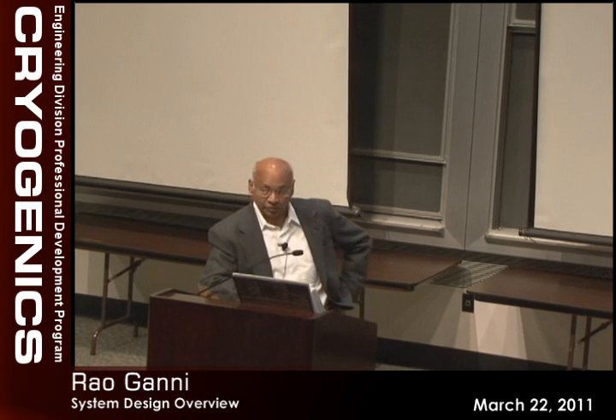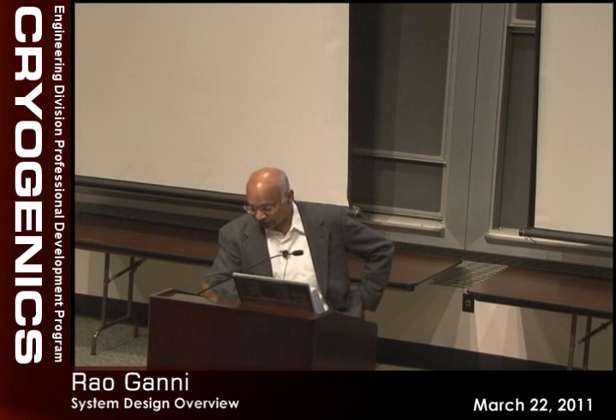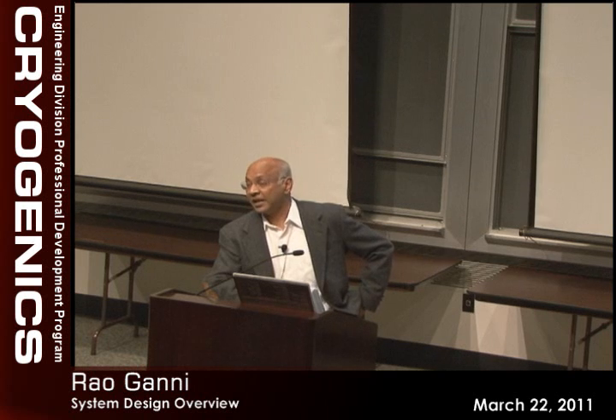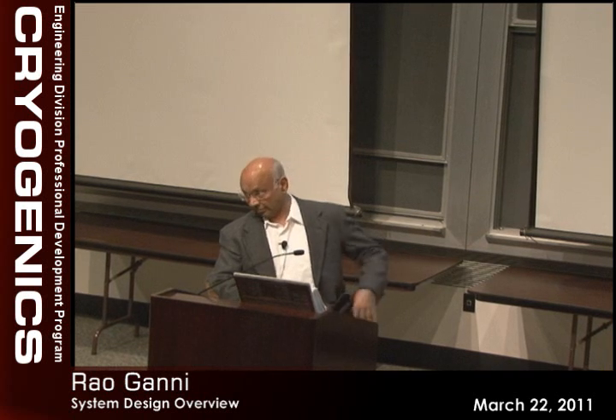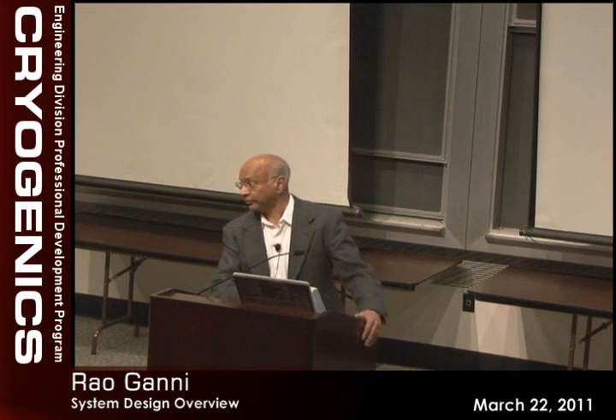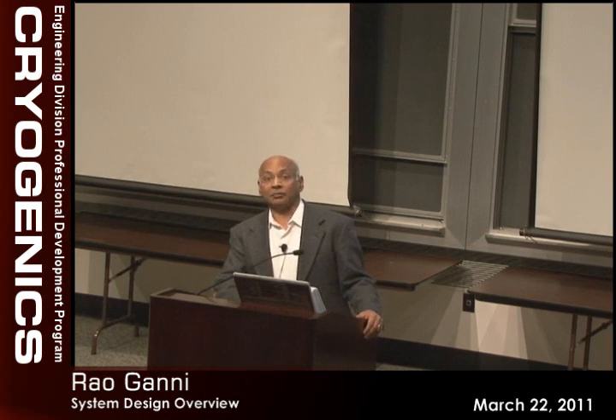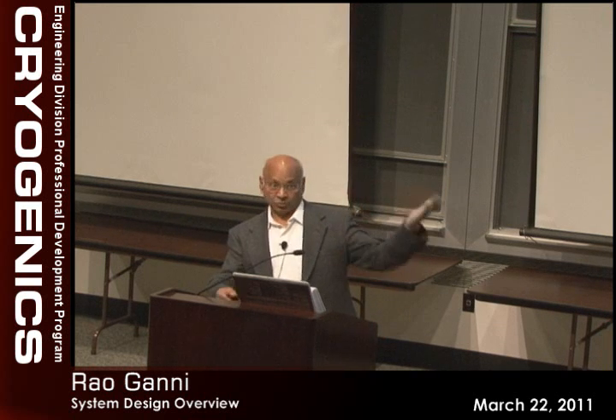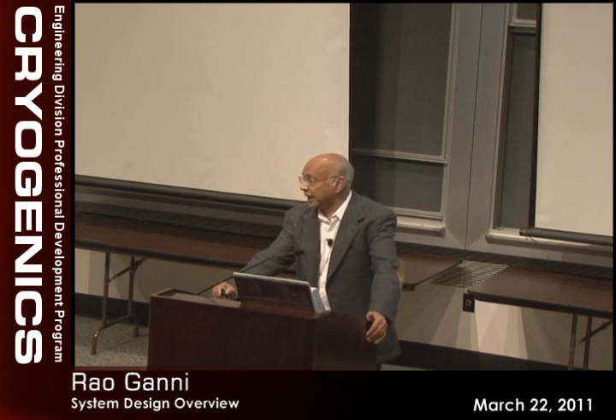The other thing we do not pay attention to is the pressure rating. It comes in a few different ways. One is that there are places where we need a very high pressure rating, like the Bureau of Mines liquefier, which we stack in the methane field or gas field, where it has to be built explosion proof, with all the controls and everything in one and a half to 2 inch thick plates, because it has to withstand an explosion if one happens. There, we definitely need that.